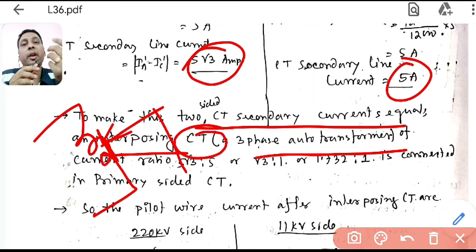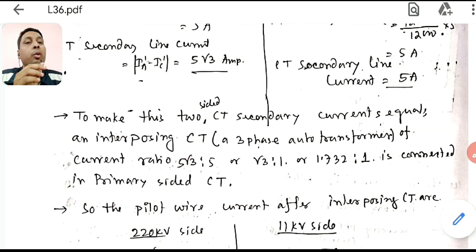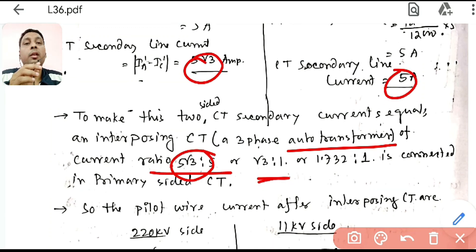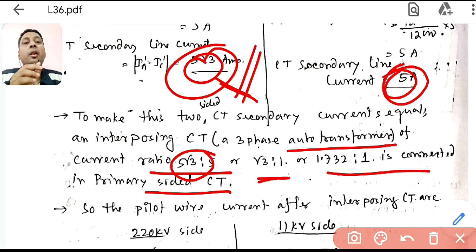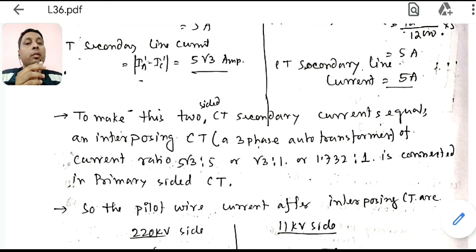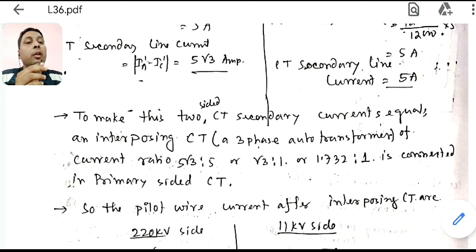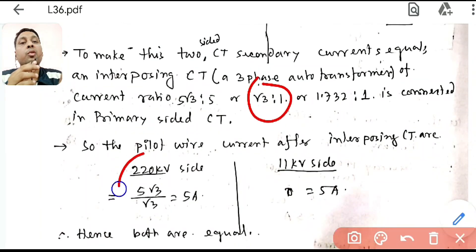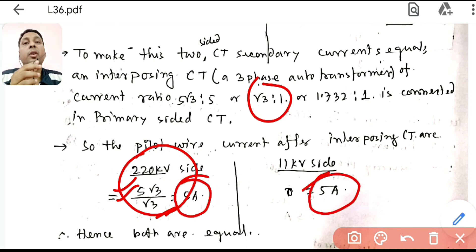Now the two sides give different pilot wire currents: 5√3 A on the 220 kV side and 5 A on the 11 kV side. To equalize them, we connect an interposing CT (auto-transformer) of ratio √3:1 on the 220 kV side. This reduces the 5√3 A current by a factor of √3, giving 5 A — matching the 11 kV side current.